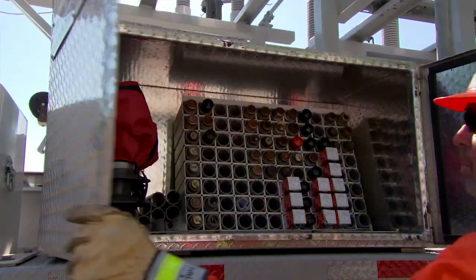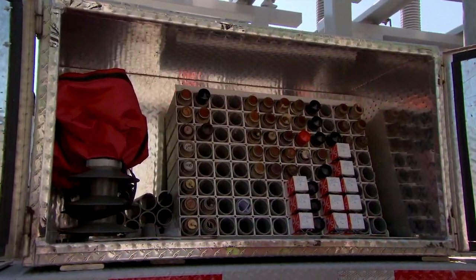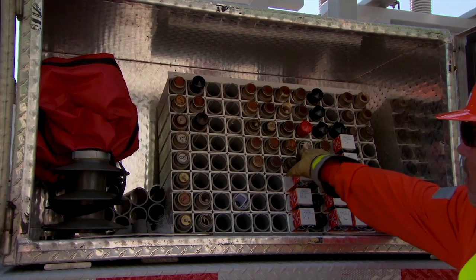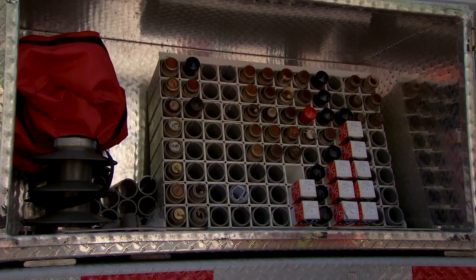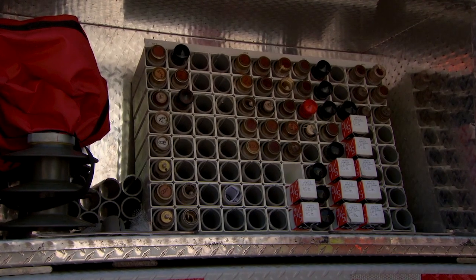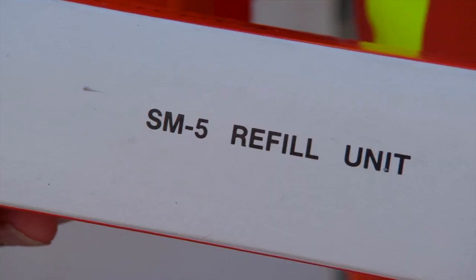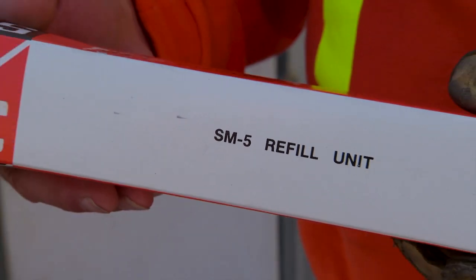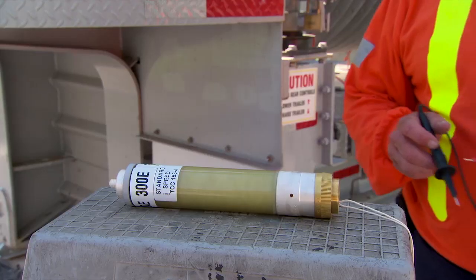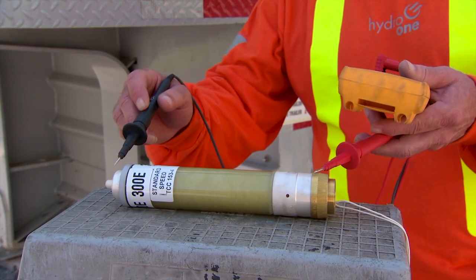Feeder protection requirements will vary from station to station and may require fuse elements to be changed. Use Appendix C in SP 1609 to select a fuse element with the proper current rating required for feeder protection. Test the fuse element for continuity with a multimeter.